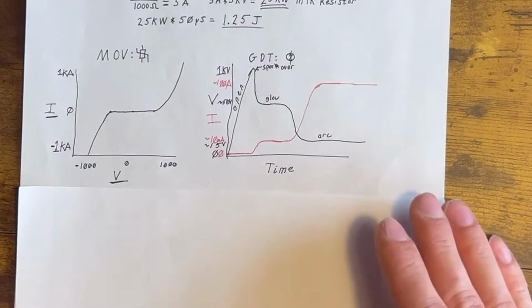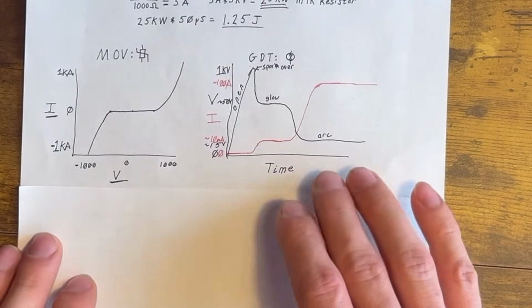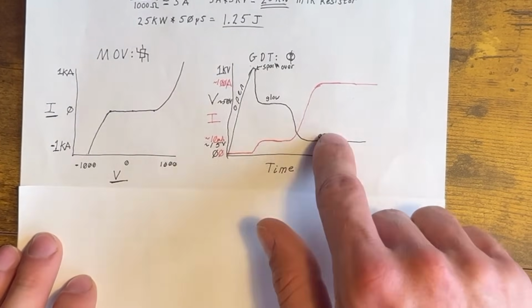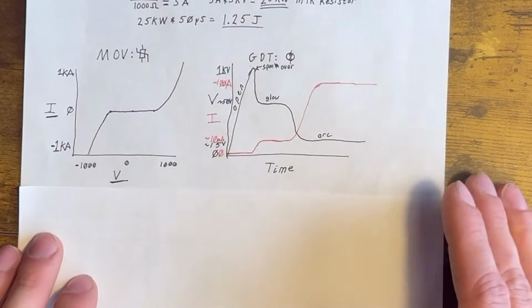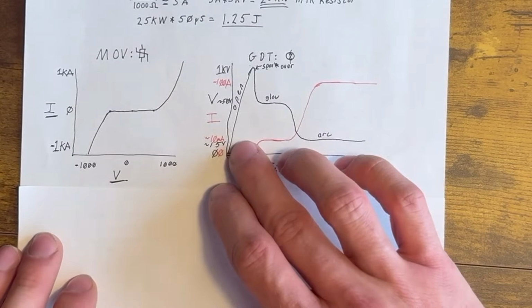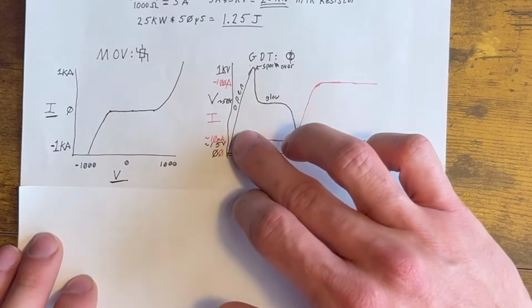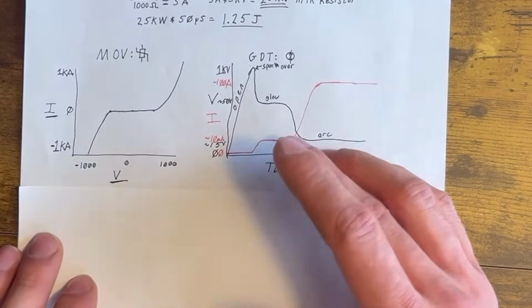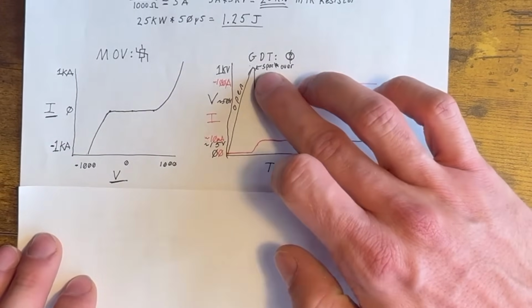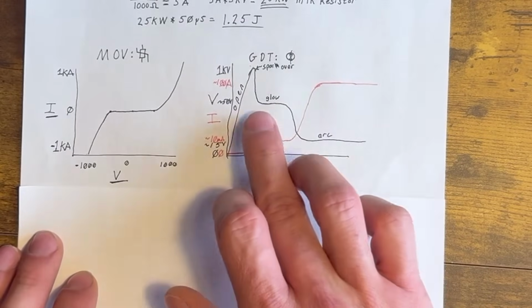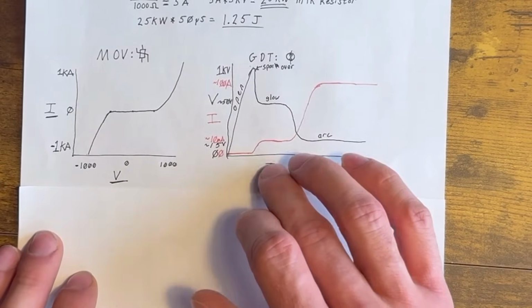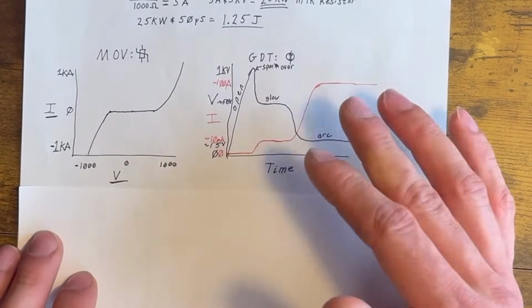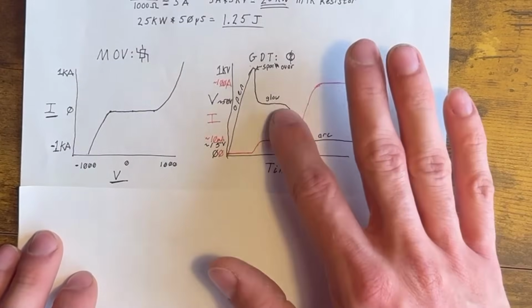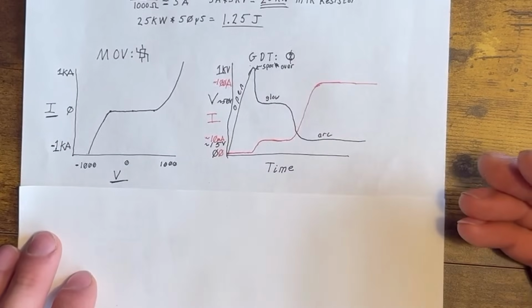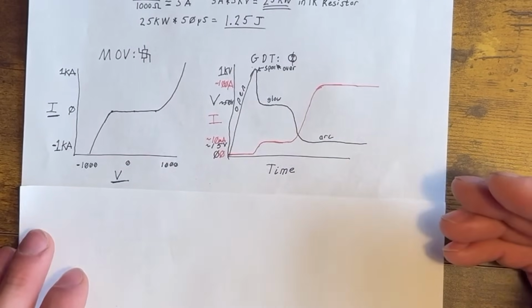A GDT is better explained in the time domain. Here we've got a chart of both voltage, shown in black, and current, shown in red, over time. At lower voltages, as the voltage is rising here, it acts like an open circuit, very little current, much like an MOV, and it has a trigger voltage, called spark over in a GDT, where it starts to conduct weakly, medium voltage and low current. A few tens of milliamps maybe for a short time, called a glow, because the GDT literally glows as the gas inside turns to a plasma.